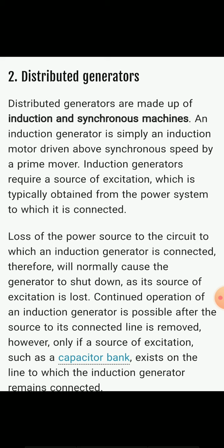So, loss of the power source to the circuit to which an induction generator is connected would normally cause the generator to shut down, as its source of excitation is lost. Continued operation of an induction generator is possible after the source to its connected line is removed. However, only if a source of excitation such as capacitor banks exists on the line to which the induction generator remains connected. Okay, thank you.